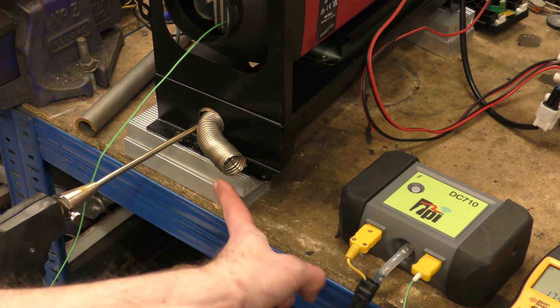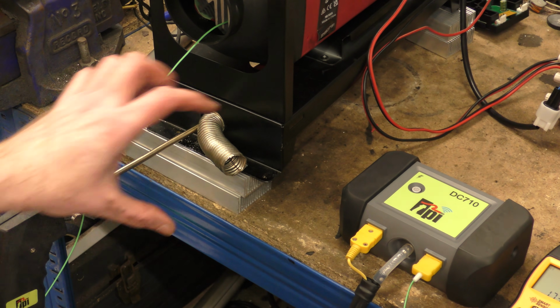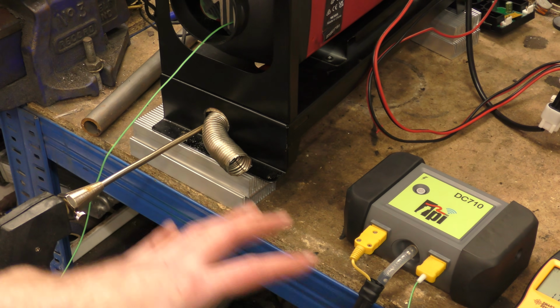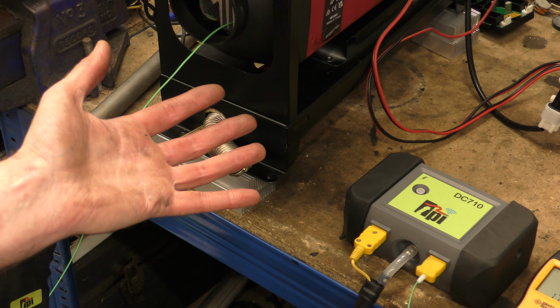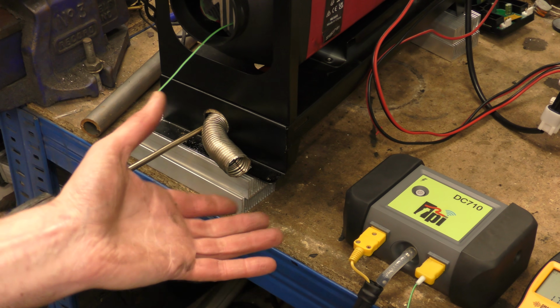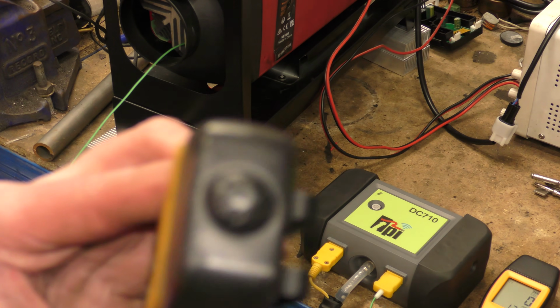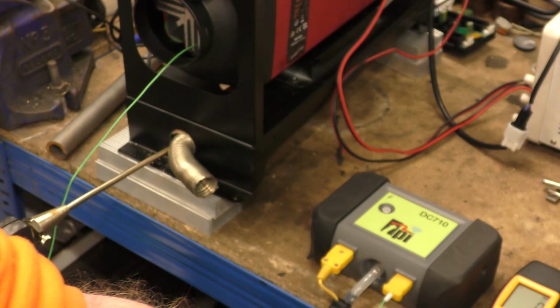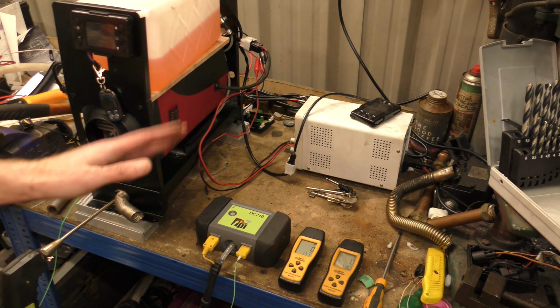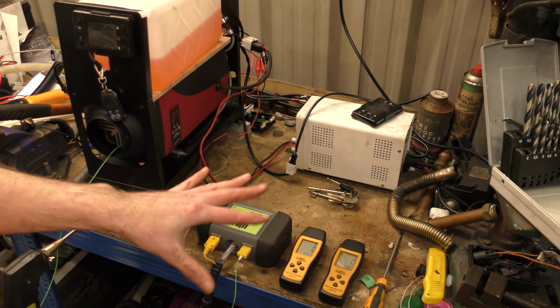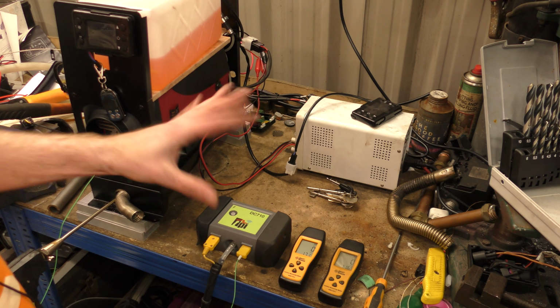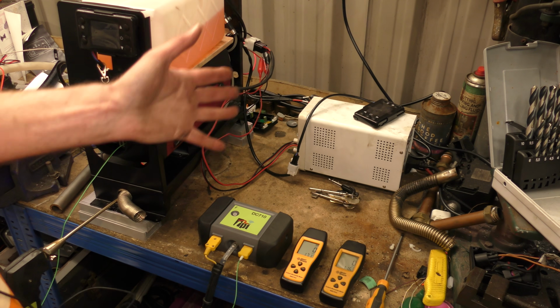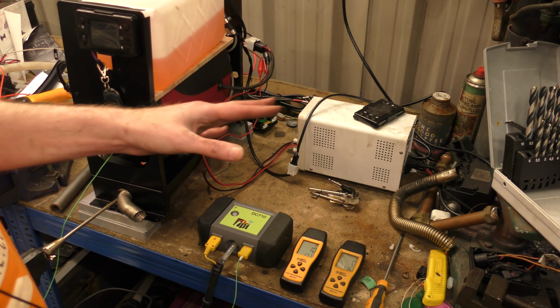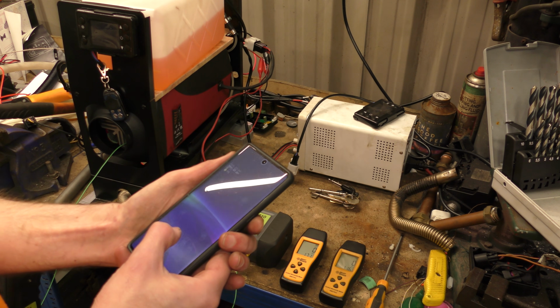We've got the rest of the exhaust coming this way, and I've got a big tin I'm going to put on the end so we can capture more of the carbon monoxide and hopefully get a better reading, without melting this again since I've already melted the end of it. Hence why I brought the brand new one, just in case. So we'll do a bit of adjustment on the fly and see how that alters the carbon monoxide, carbon dioxide, excess air, and all the other bits and bobs.